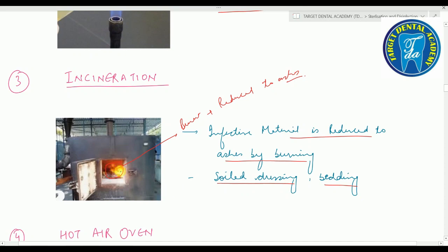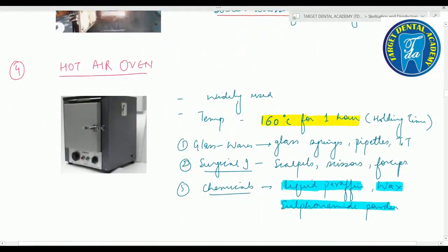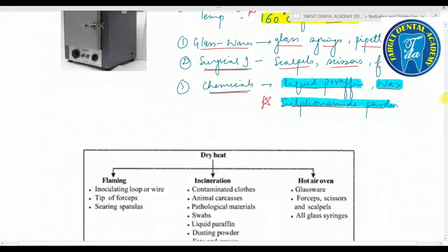Last method is the hot air oven — the most widely used method of dry heat sterilization. The important temperature is 160°C for one hour — this is the holding time. You can sterilize glassware products like glass syringes, pipettes, and test tubes; surgical instruments like scalpels, scissors, and forceps; and chemical products like liquid paraffin, wax, and sulfonamide powder. The key temperature to remember: 160°C for one hour.